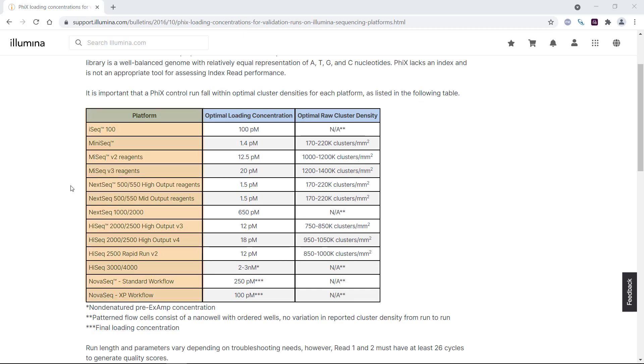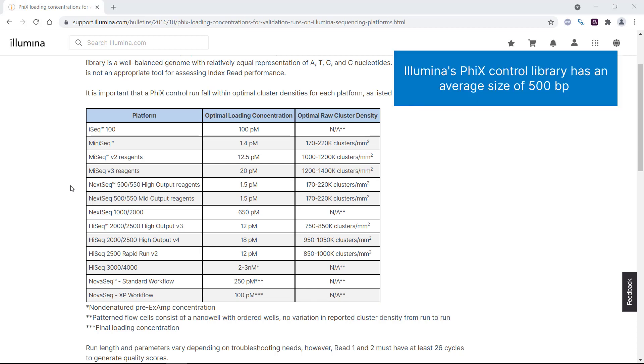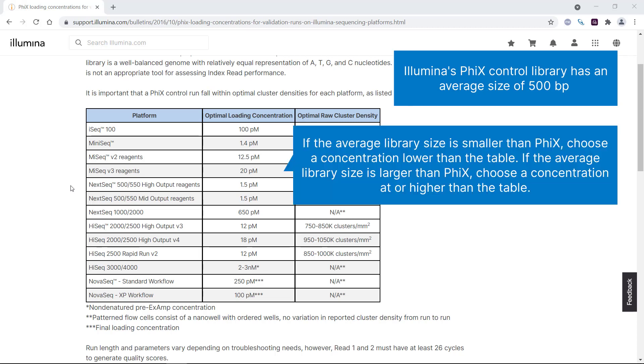The table shows the sequencing platform on the left, optimal PhiX loading concentration in the middle, and the resulting optimal cluster density range on the right. If your library average size is smaller than PhiX, choose a concentration lower than what's listed in the table. If your average library size is larger than PhiX, choose a concentration at or higher than what's listed in the table.